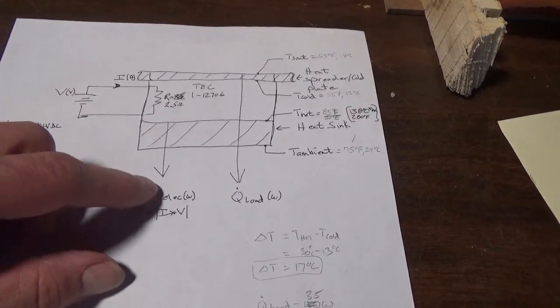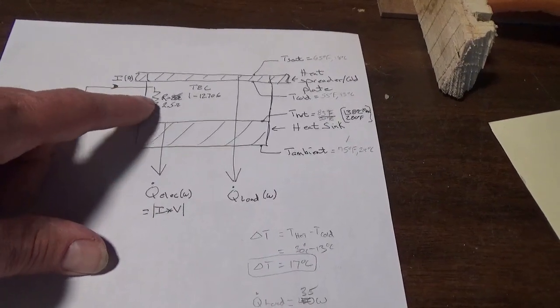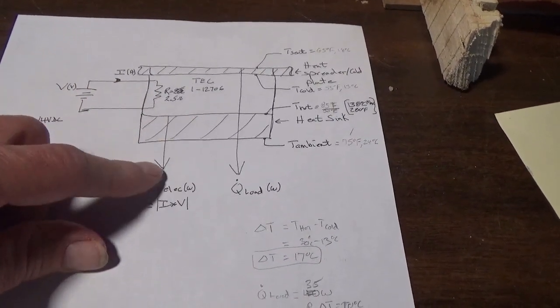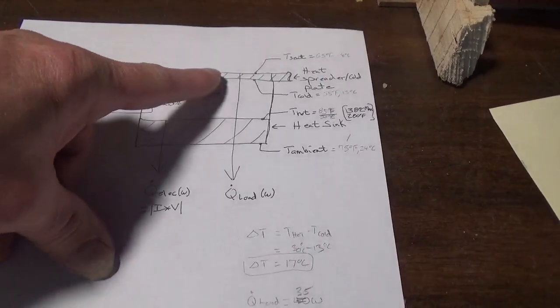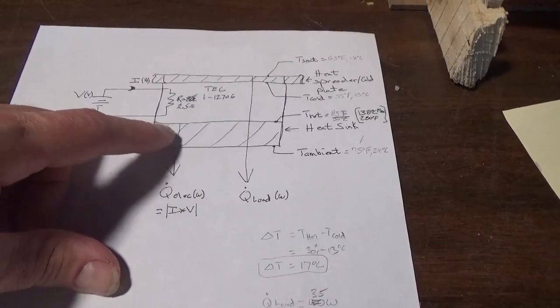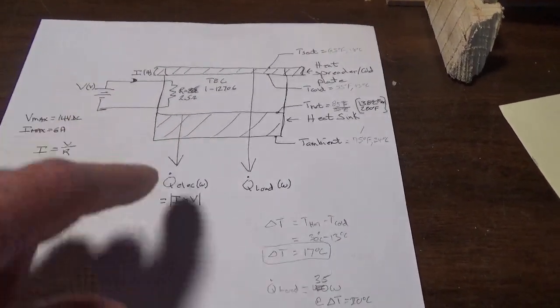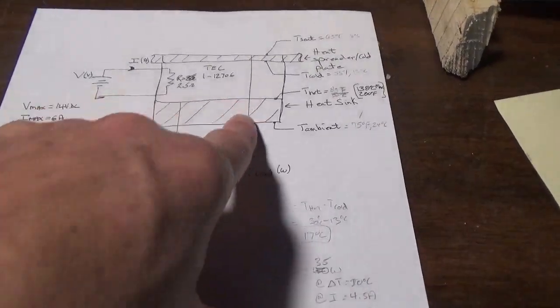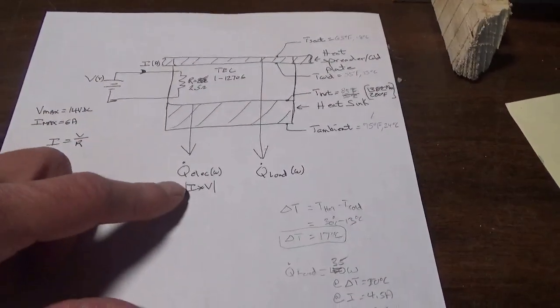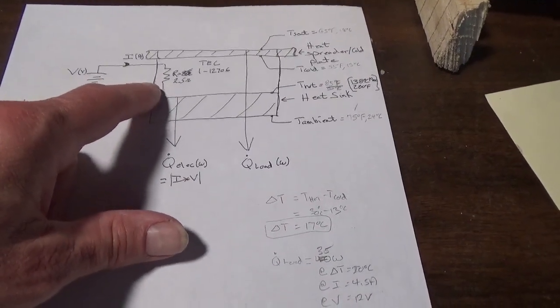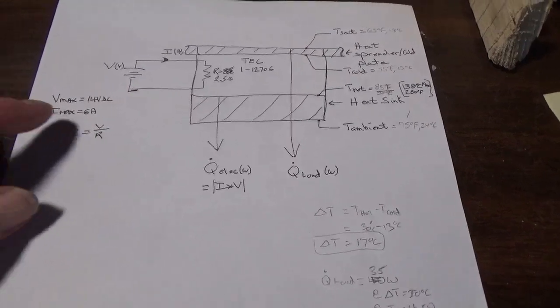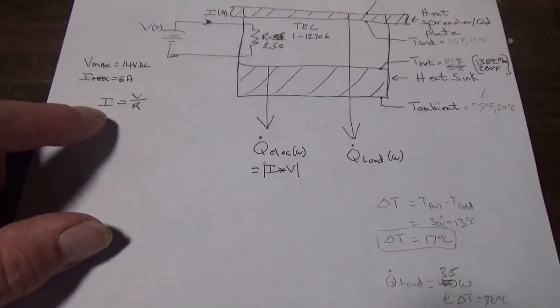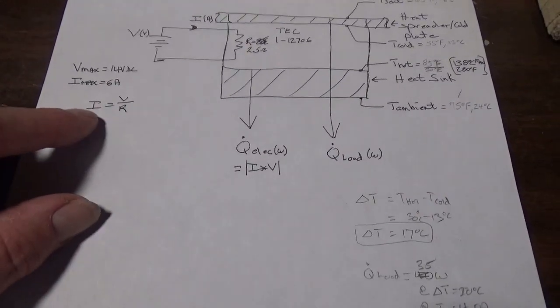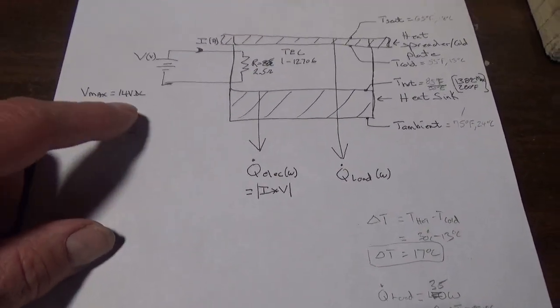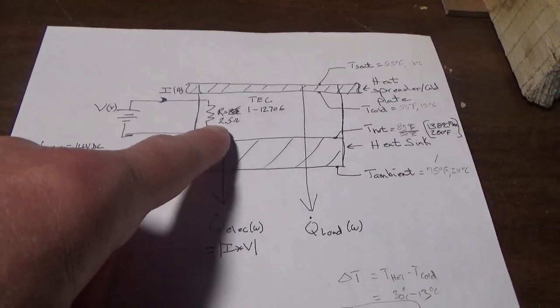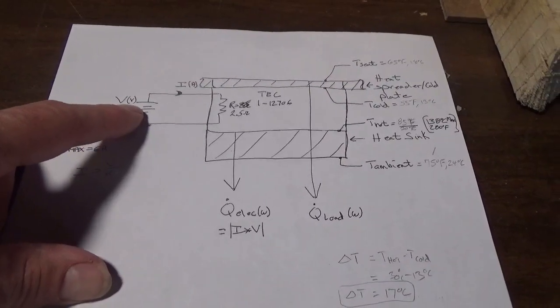There's also this part where you're putting in electrical power, so there's heat that has to get dissipated just from this load, not whatever load you're bringing off the cold plate. This is in addition to — there's two parts of the heat. You have the heat you're trying to dissipate from your cold plate, and you have the heat you need to dissipate from the amount of current you're putting into this unit. Maximum voltage, they said, was 14 volts, and maximum current is 6 amps. Ohm's law, I equals V over R, so the resistance is effectively fixed at 2.5. You put more voltage in, you're going to get more current.